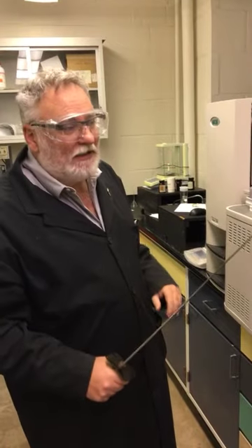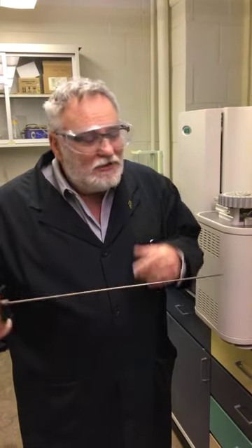We load our ceramic boat, and again, that is the correct term. I have a balance over here. It's a high precision, highly accurate balance. It goes to 5 decimal places, but the ASTM says we utilize 4. So when I push a button on the balance, it tells the computer this is the date and mass of the sample.